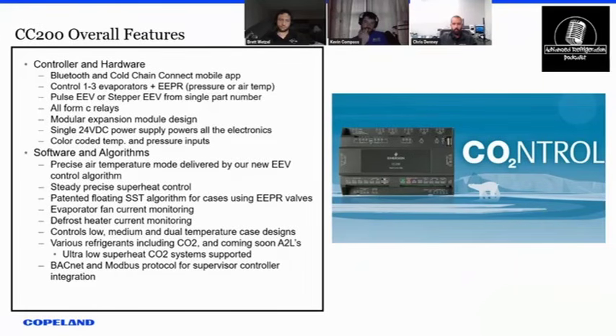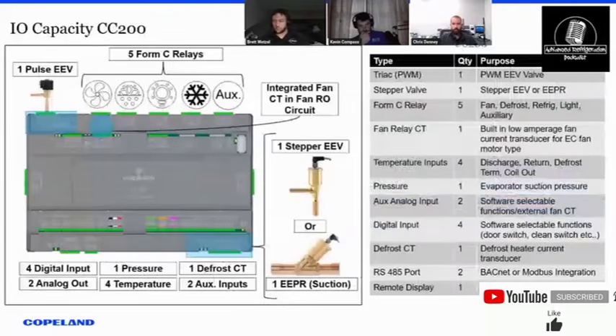On the CO2 side, we recently added support for ultra low superheat. A couple OEMs are trying that out. Kysor Warren EPTA specifically has their ultra low superheat rack design, so we're able to be compatible with them and any other OEMs that are doing that.